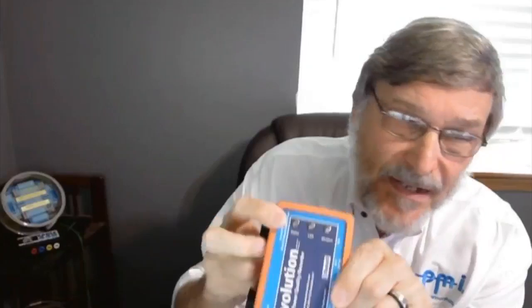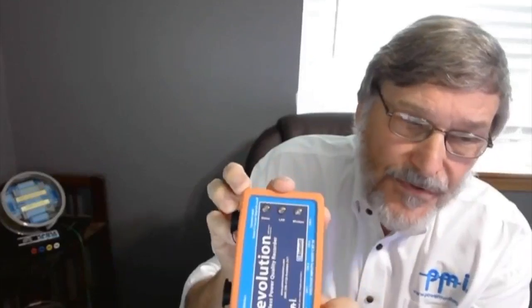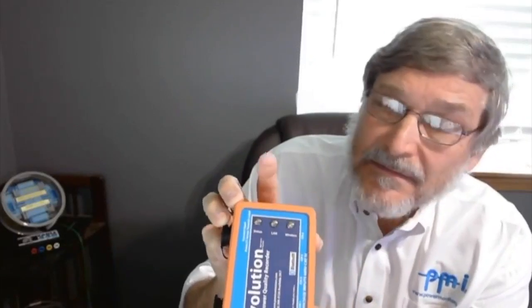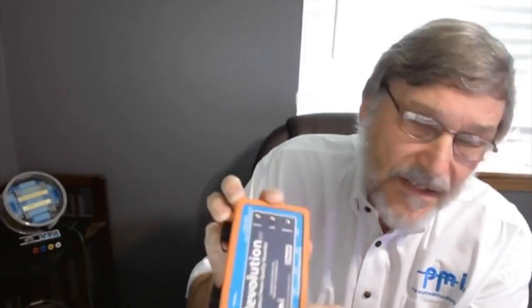And for the recorders, the one thing you want to make sure is the status LED is flashing. If the status LED is not flashing, the recorder is not recording. So make sure that LED is on. The Revolutions have a LAN for the Ethernet that flashes kind of a heartbeat. And if you have the cellular, the wireless LED will be on.